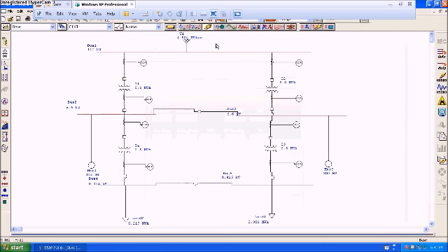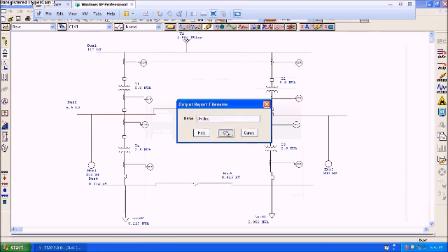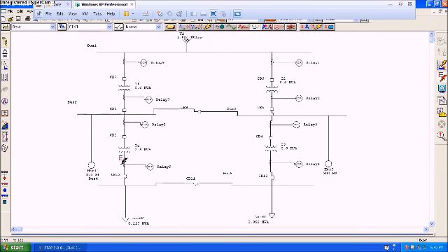This is a unique feature of ETAP: for creating a star view we have to select the circuit and click over here, and it will automatically give us the graph. This is the graph. I will separate this over here. Relay 4 and 6 are tripping first. There the time is 0.169 second, and then relay 3 and 5 are tripping at 0.556 second, and relay 2, 7, 9, 1 is not tripping for this fault.